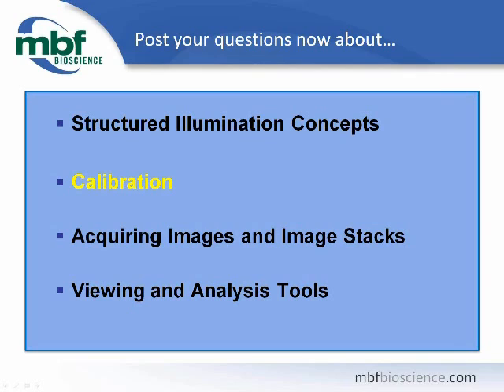If you notice your grid focus has declined in quality, you may want to readjust those positions and save over the old. Those can vary from staining protocol to staining protocol, so once set they should be stable, but when you switch stains it might be different. If you purchase an Apatome with Stereo Investigator or Neuralucida, our installation team will perform the phase and focus calibrations so you can immediately start using your system. The calibration does not need to be done each time you image — you'll set it once and it should remain suitable for multiple imaging sessions.